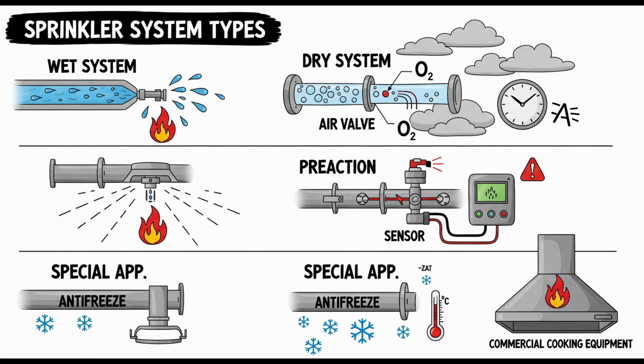The standard gets into very specific piping and valve arrangements for antifreeze systems, often referencing figures, and it seems heavily focused on preventing backflow into the potable water supply. Yes, absolutely. Preventing contamination of the municipal or building water supply is a major health and safety concern when you're connecting piping filled with chemicals like antifreeze to it. The specific arrangement of valves, check valves, and required backflow prevention devices depends on the setup, with different configurations outlined in figures in the standard.